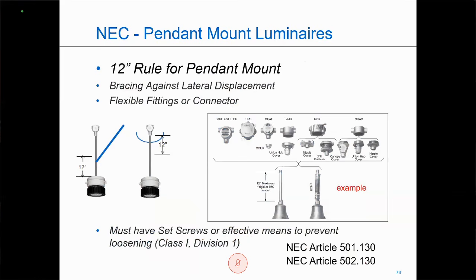This is one that we had discussed previously with the quiz, where I have to protect against lateral displacement anytime I have 12 inches or longer of a pendant. The whole thing here is if something were to come by and hit that conduit, the conduit could spark, cut a conductor, which can arc. So here's where I was referring to the permanent effective brace coming down to within 12 inches of where the pendant stem connects to the fixture, or where we have flexibility within 12 inches of where the pendant stem connects to the junction box. This flexibility in this picture happens to be the junction box with the flexible hanger with it. Usually these flexible hangers give you anywhere from 11 degrees to 20 degrees of movement, depending on the particular design.